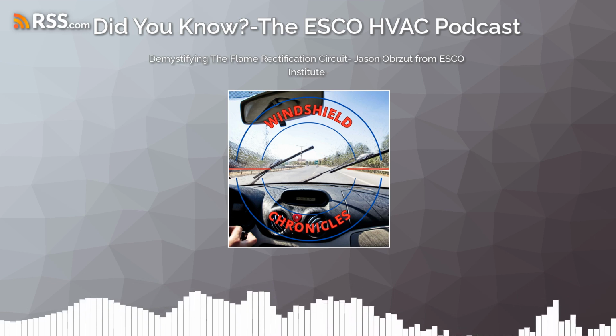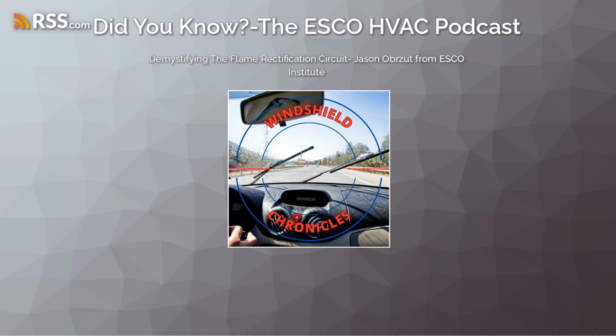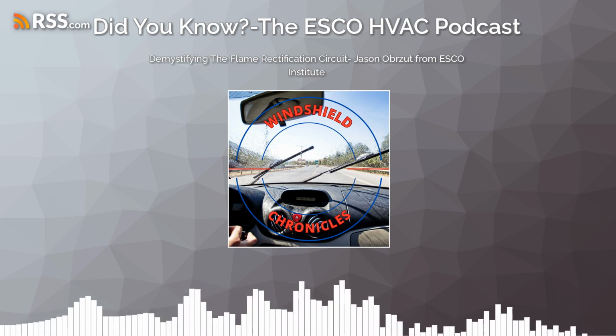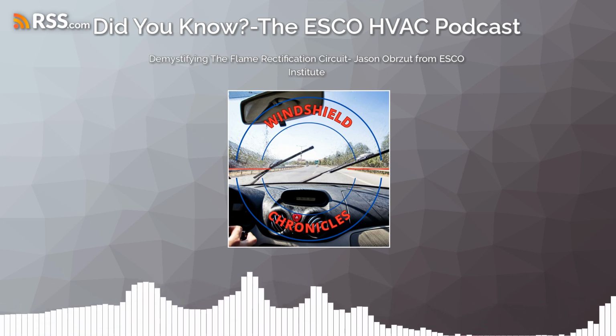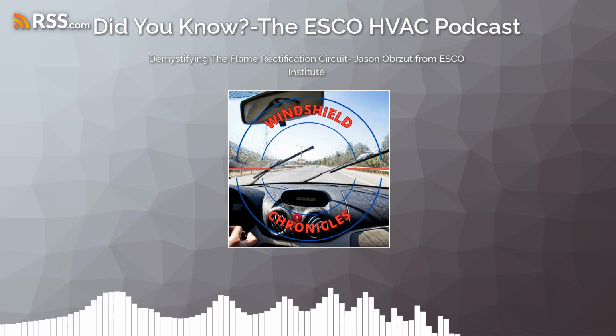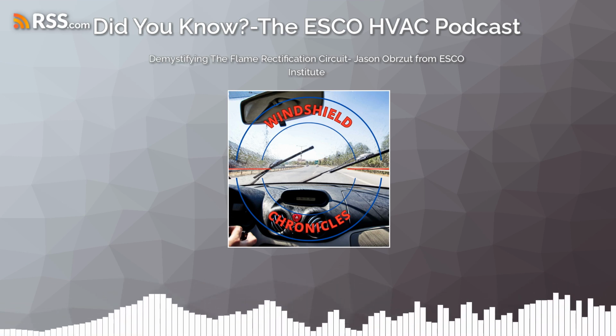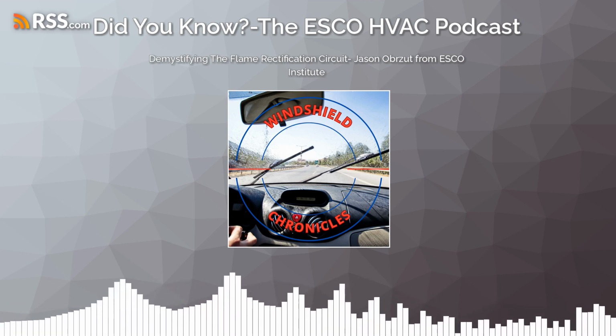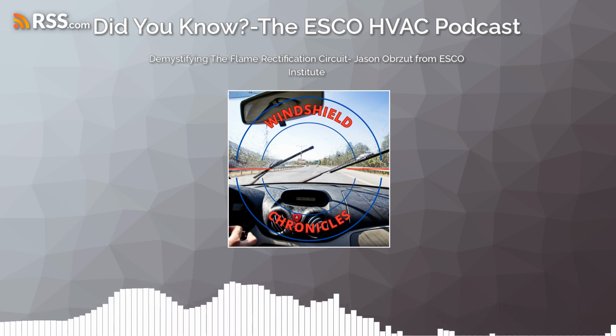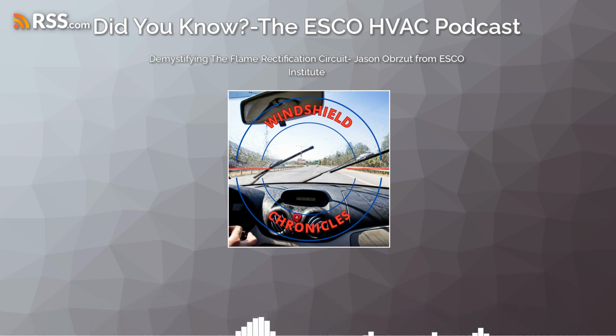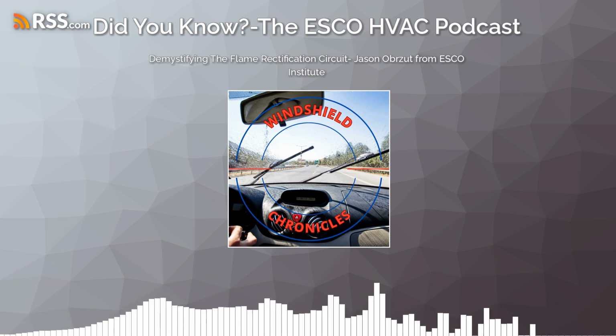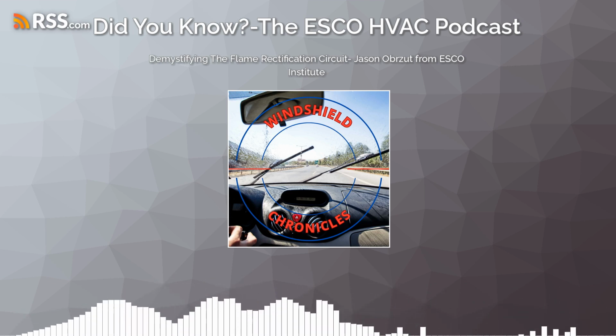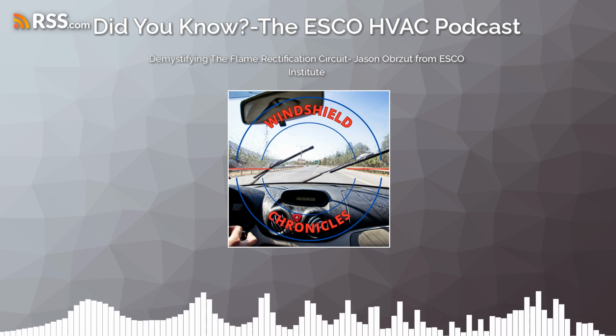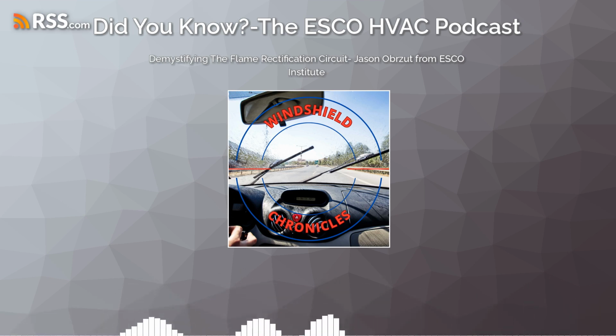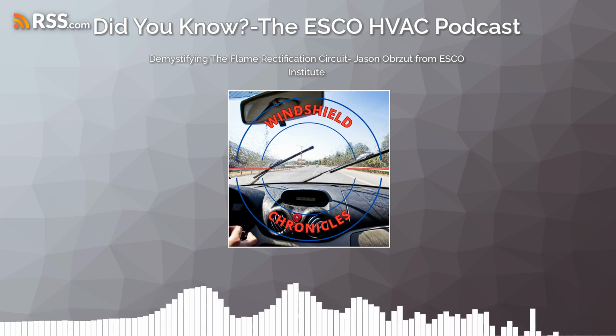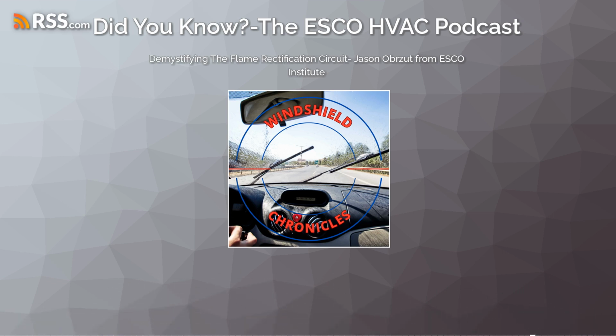So with rectification, we absolutely are not relying on heat, right? So there's a misconception that we need to break real quick. With flame rectification, we are actually completing an electrical circuit, right? So we are actually going to apply voltage onto a flame rod. We're going to pass through the flame. We're going to go through this process of rectification, and we'll help you understand why it gets that name, what it's actually doing. And then we're going to return back on our ground. And so we have to stop for a minute and go, well, wait a minute. Maybe I wasn't explained that that's what happens with this flame sensor.